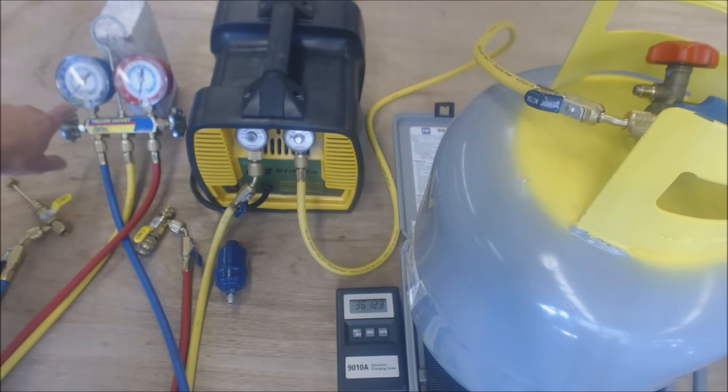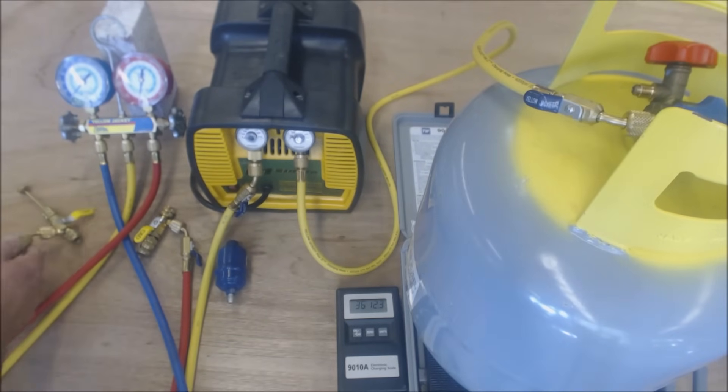You're sucking the refrigerant down, so if it's 70 degrees and the system's off and you're working with 134A, you're going to have right around 72 PSIG. It'll take a little bit to recover it down to that level, but that's how you do it. You can use these core removal tools so that it doesn't take as long and your Schrader valve is not in the way. You don't have to use these—you can just go ahead and connect in and just recover right through your Schrader valve. That's fine too.